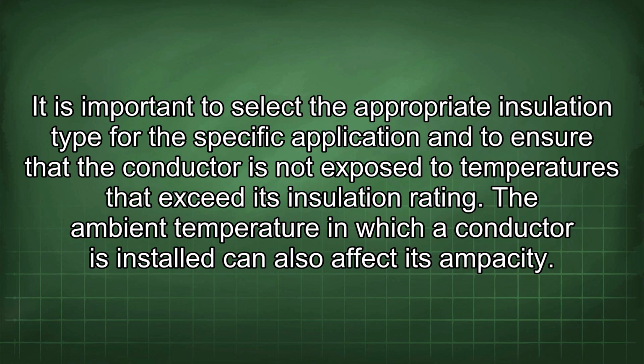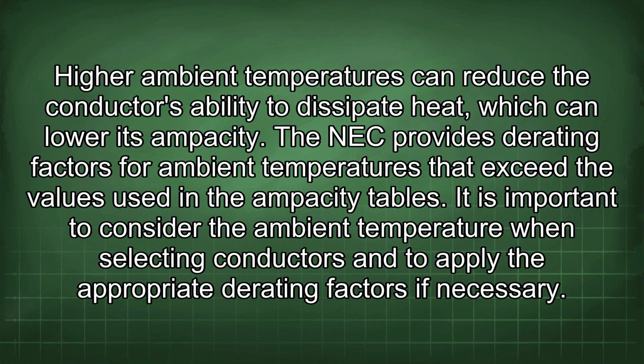The ambient temperature in which a conductor is installed can also affect its ampacity. Higher ambient temperatures can reduce the conductor's ability to dissipate heat, which can lower its ampacity. The NEC provides derating factors for ambient temperatures that exceed the values used in the ampacity tables. It is important to consider the ambient temperature when selecting conductors and to apply the appropriate derating factors if necessary.